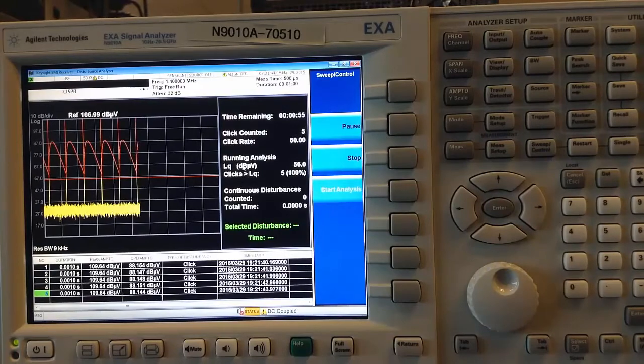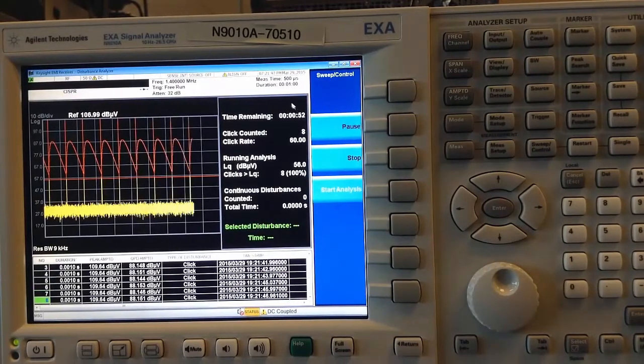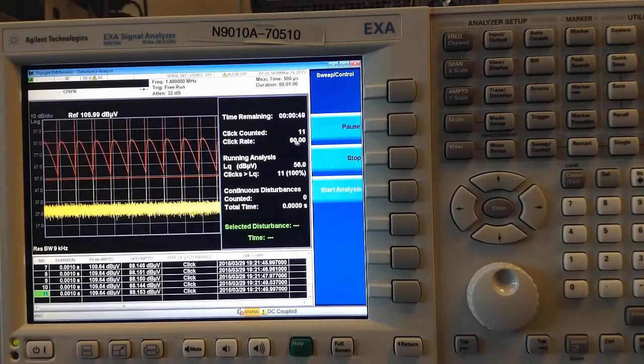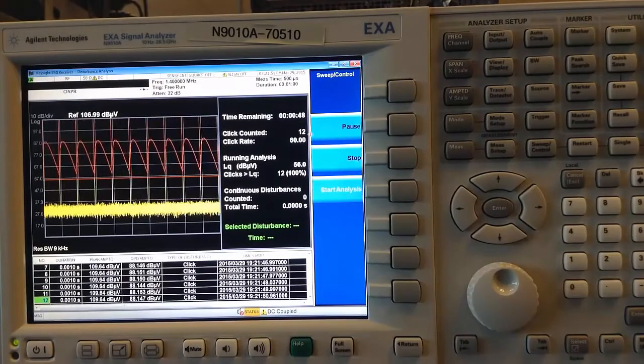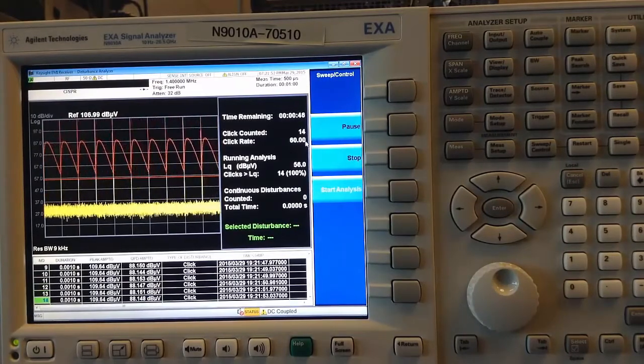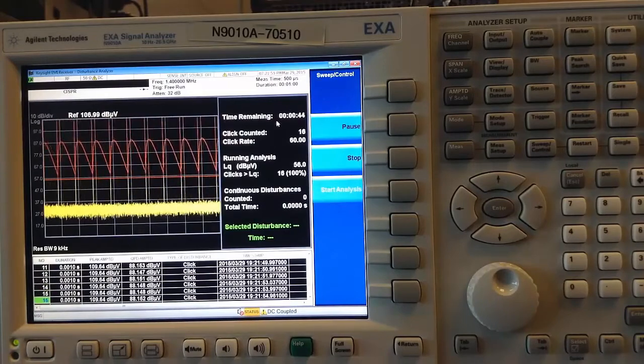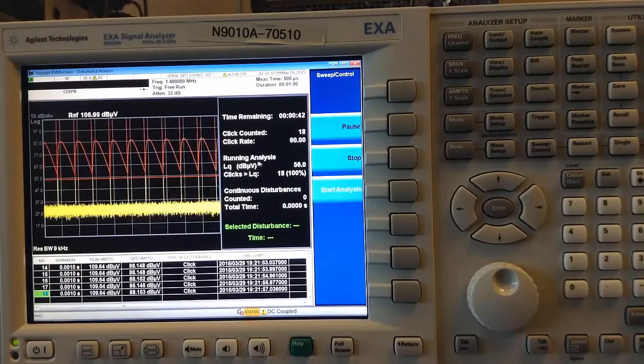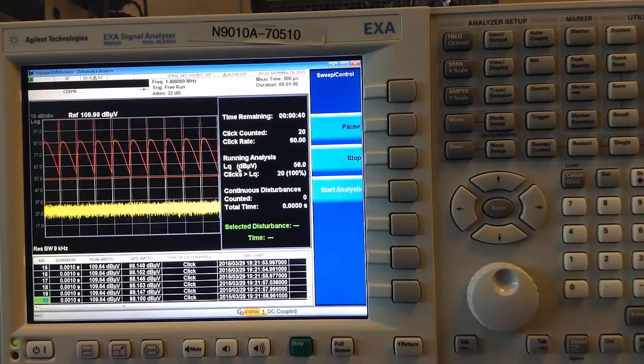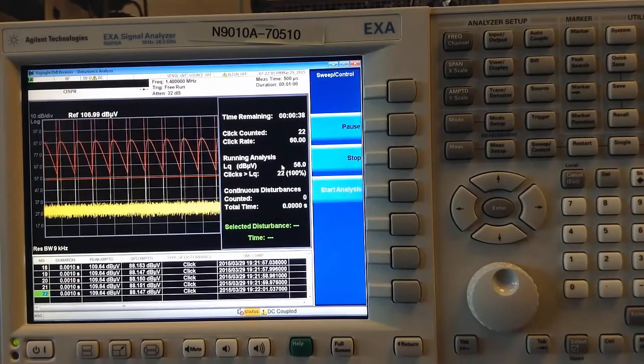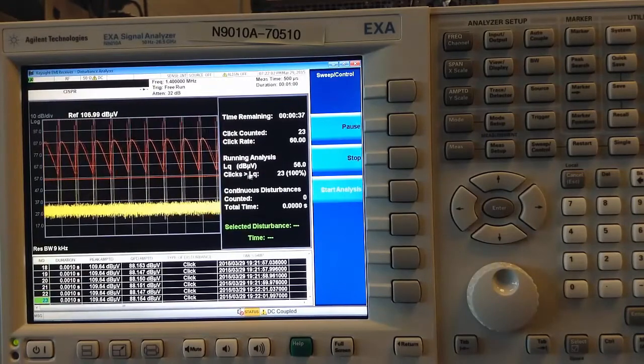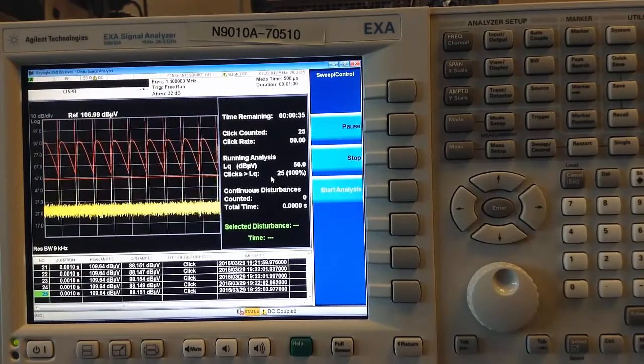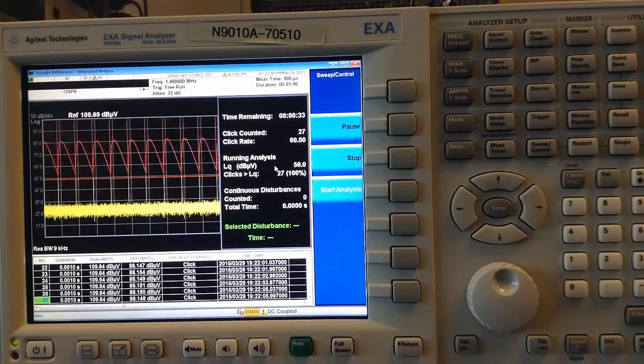As the measurement continues, I can observe the timer counting down, the number of clicks being counted, and the click rate as determined by the combination of these two. A running analysis showing the click limit, which we had selected earlier, as well as how many clicks are exceeding the relaxed click limit.